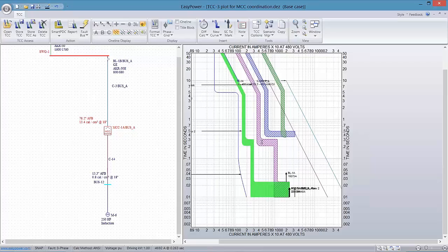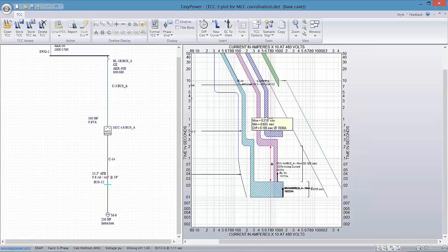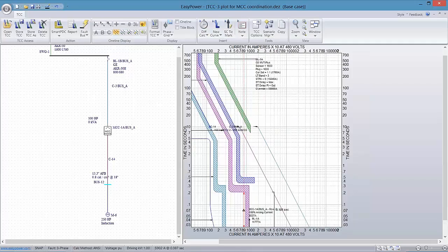difference calculations. Now here, I guess I want to go back and look at my faulting current. And as we center our faulting current over the arcing current, we can align and calculate all the differentials between each of the breakers.